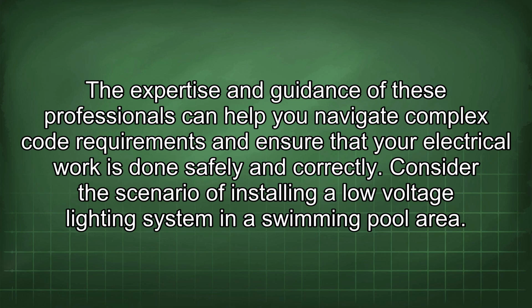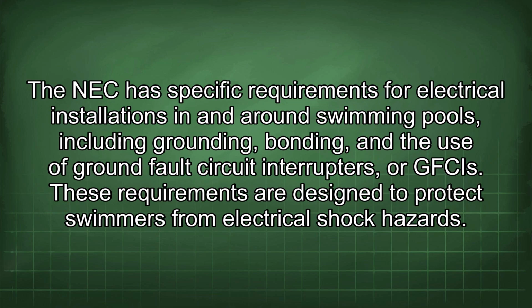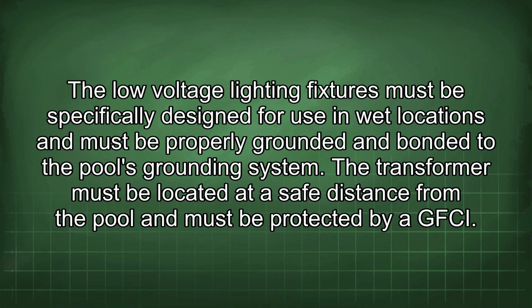Consider the scenario of installing a low-voltage lighting system in a swimming pool area. The NEC has specific requirements for electrical installations in and around swimming pools, including grounding, bonding, and the use of ground fault circuit interrupters, or GFCIs. These requirements are designed to protect swimmers from electrical shock hazards. The low-voltage lighting fixtures must be specifically designed for use in wet locations and must be properly grounded and bonded to the pool's grounding system.